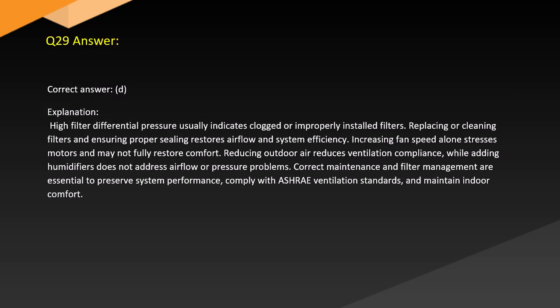Answer. Correct answer. D. Explanation. High filter differential pressure usually indicates clogged or improperly installed filters. Replacing or cleaning filters and ensuring proper sealing restores airflow and system efficiency. Increasing fan speed alone stresses motors and may not fully restore comfort. Reducing outdoor air reduces ventilation compliance, while adding humidifiers does not address airflow or pressure problems. Correct maintenance and management are essential to preserve system performance, comply with ASHRAE ventilation standards, and maintain indoor comfort.